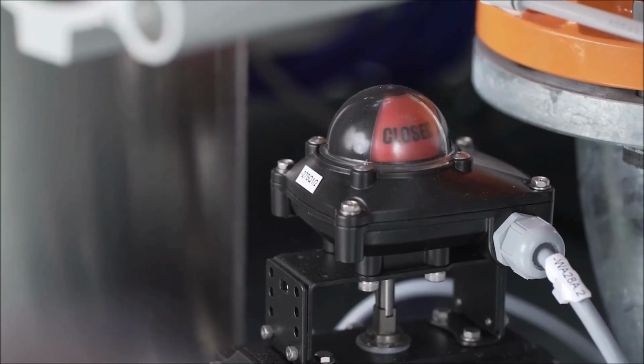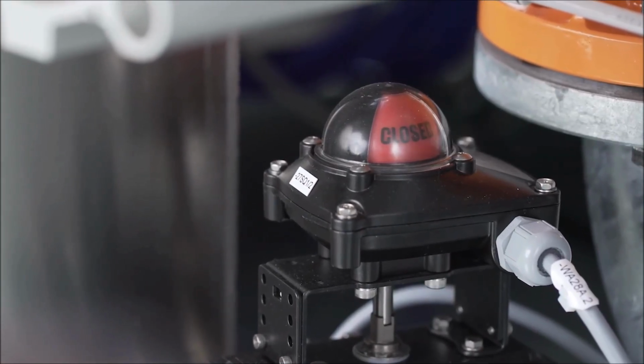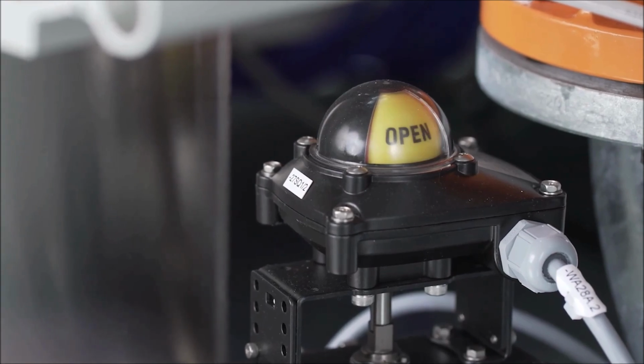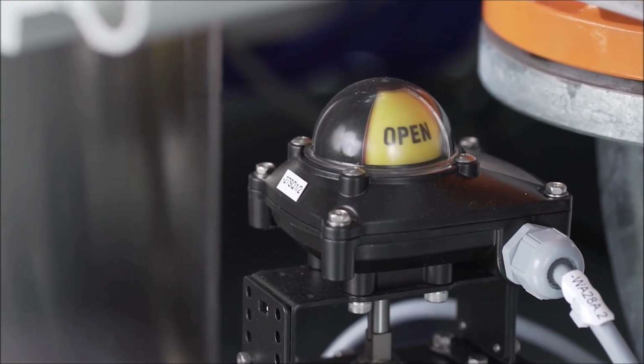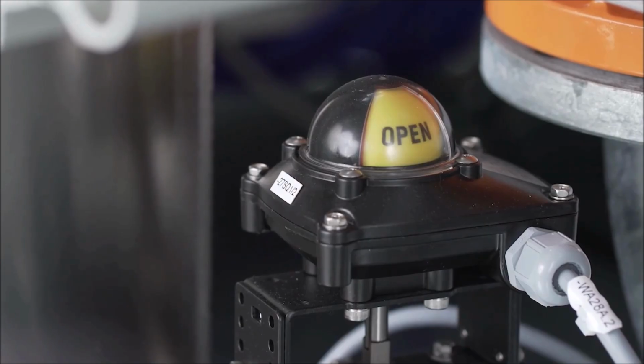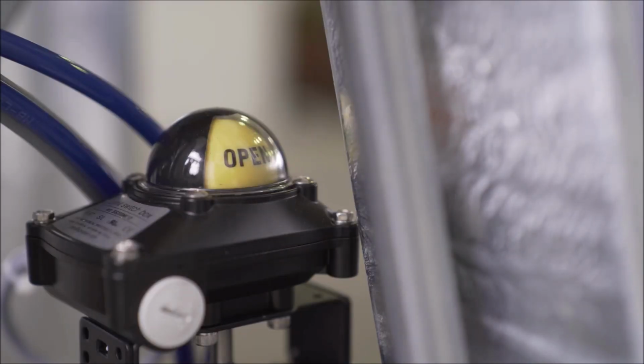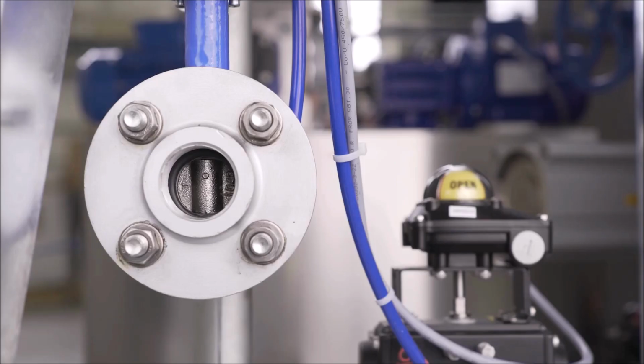In order to create a solution that is increasingly reliable and independent from the operator, dedicated switch boxes have been installed on all the valves that manage the exchange between the sludge during the pressing cycles and the water during the washing cycles. The use of switch boxes guarantees the correct execution of the operations in all different phases of the dehydration and washing processes.